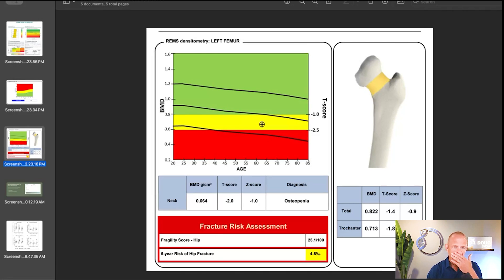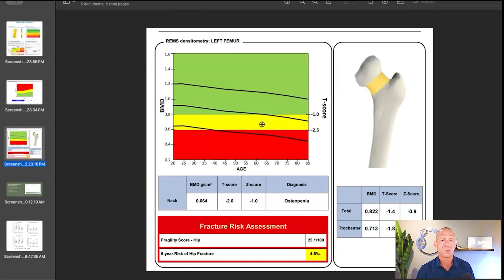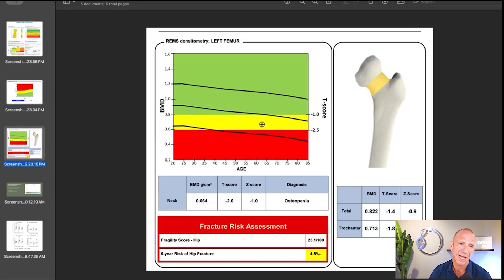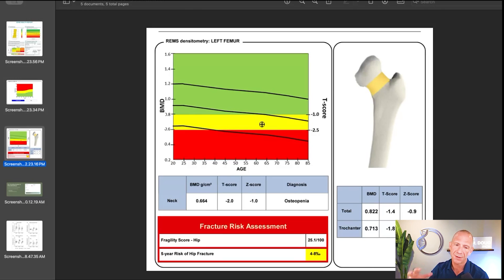Lastly, we have REMS — an ultrasound device becoming more common in the United States and Europe. REMS gives you a T-score but also a fragility score, so it helps you understand both quality and quantity. The T-score graph looks a lot like a DEXA graph — you get a T-score and Z-score. Important: you would not use REMS bone mineral density to compare to DEXA. Even on DEXA it needs to be the same machine, so comparing BMD across different technologies is invalid. If comparing, use T-score — but remember these are different technologies, so a DEXA of negative 3 and REMS of negative 2 doesn't mean you've reversed osteoporosis.